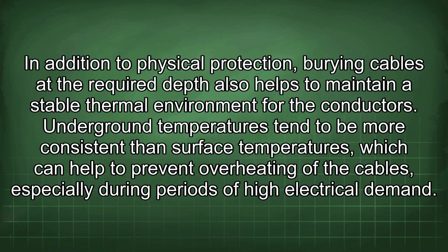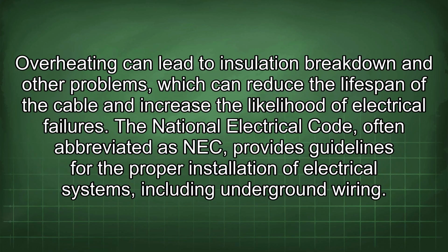In addition to physical protection, burying cables at the required depth also helps to maintain a stable thermal environment for the conductors. Underground temperatures tend to be more consistent than surface temperatures, which can help to prevent overheating of the cables, especially during periods of high electrical demand.